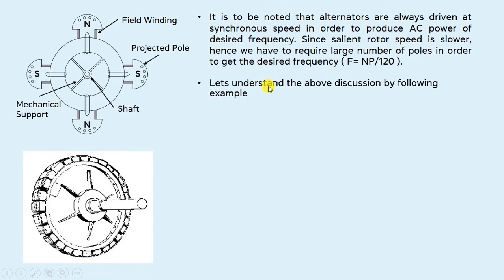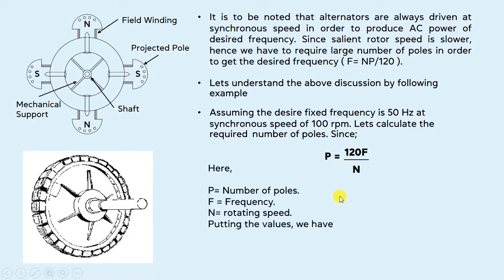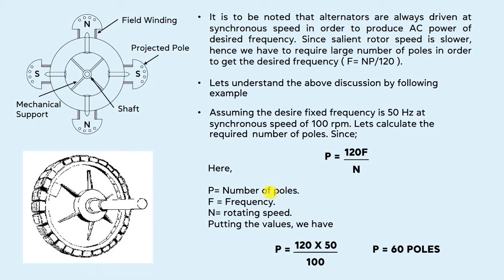Let's understand this point by the following example. Assuming that the desired fixed frequency is 50 Hz at a synchronous speed of 100 RPM, we have to calculate the required number of poles. Using the formula F = NP / 120, since we have to calculate the number of poles, P = 120F / N. Putting in the values, we get 60 poles. So if the alternator runs at 100 RPM with a fixed frequency of 50 Hz, the number of poles required is 60. Therefore, a large number of poles is required in the case of a salient type rotor, since they cannot be run at higher speed.